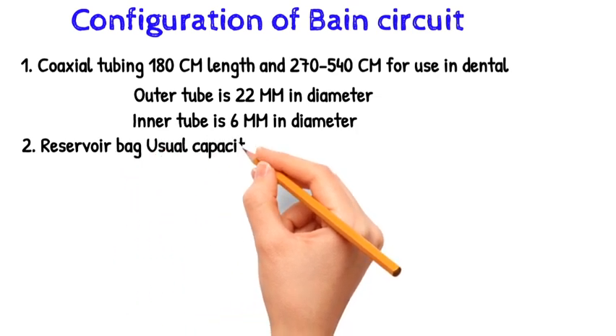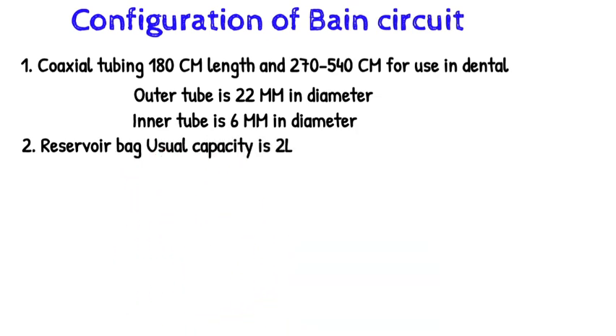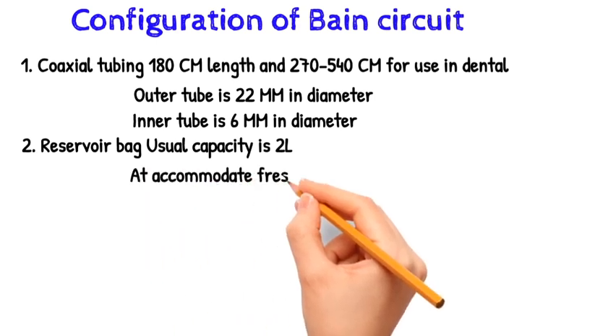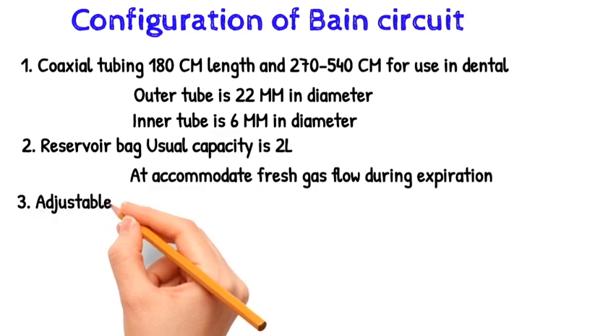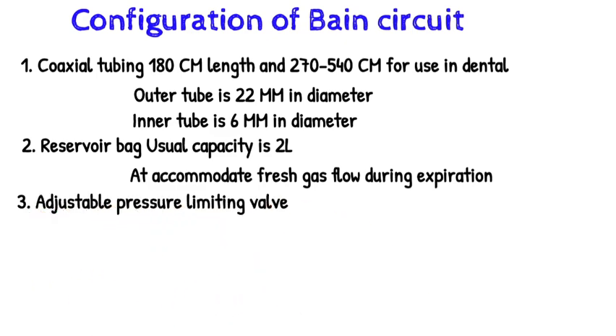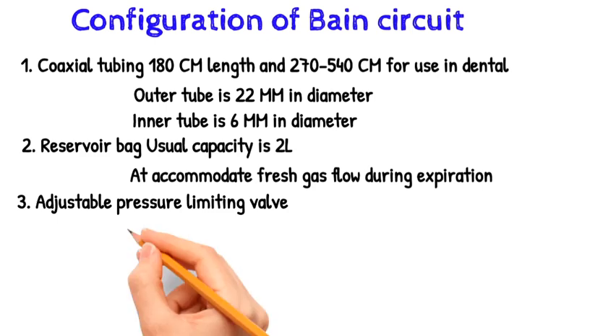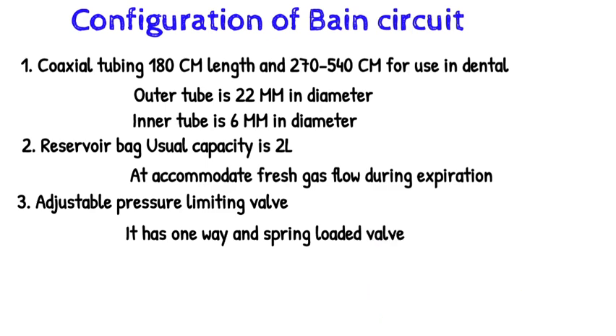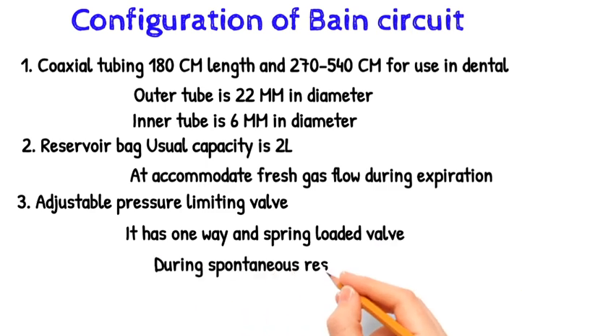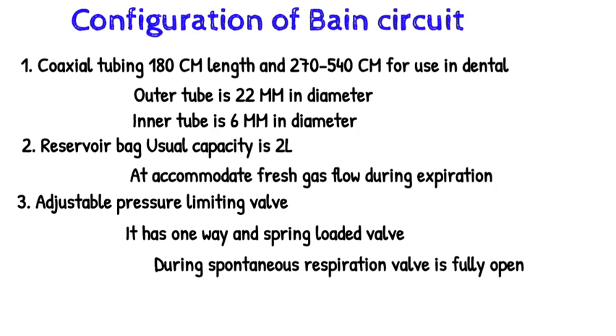The reservoir bag has a usual capacity of 2 liters, made from antistatic and latex-free rubber, and accommodates fresh gas flow during expiration. The adjustable pressure limiting (APL) valve is always located away from the patient and is adjustable. It has a one-way, spring-loaded valve. During spontaneous respiration, the valve is fully open; during controlled respiration, the valve is adjustable with a dial.